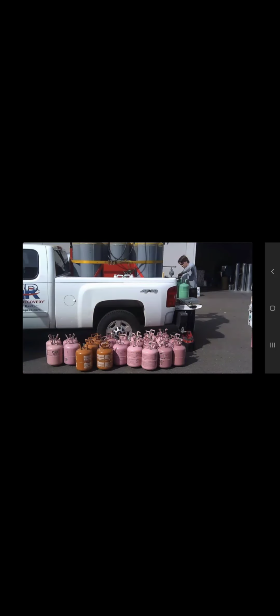How do we keep track of that? There's so many different sizes. There's pumpkins, there's tiny ones. There's these big boys in the back of the truck. How do we keep track of the 80% rule? The big ones in the back of this truck will have a float in them. Okay, they got a gauge right on them. You hit 80%, stop adding refrigerant, they go to the reclamation facility.